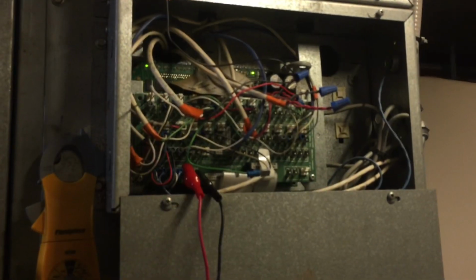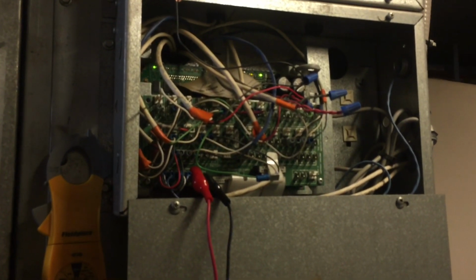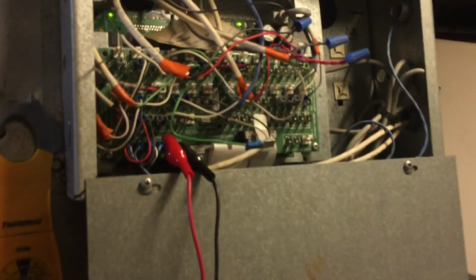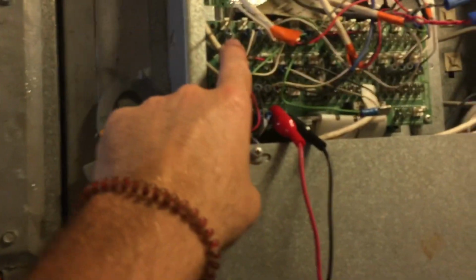So it turns out that my actuator had 24 volts in common to power it up, but since there was no ground and the signal is supposed to share the common or ground, it didn't have a ground, because the output that comes from here comes from the first transformer, and the actuator is powered from the second transformer.